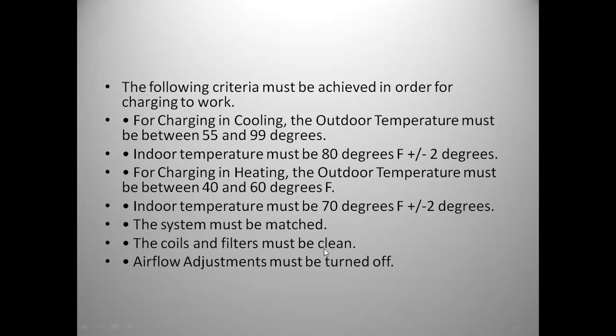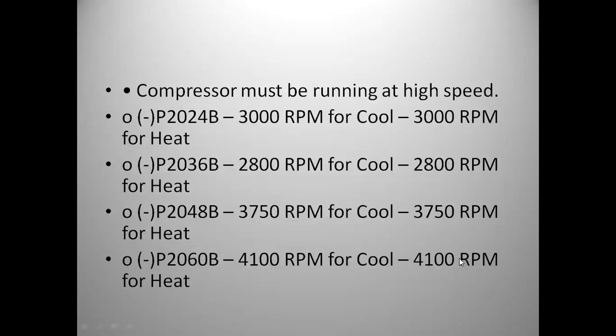The coils and filters must be clean. If they're not clean, it will skew your readings and affect your charge. And then all airflow adjustments must be turned off. And this is a big one. Ran into this the other day. Similar to a two-stage air conditioner or two-stage heat pump, these inverters must be running at the highest speed in order to check or adjust charge. If you're not running at the highest speed and it's not stabilized, by the time it does run at high speed and does stabilize, you may very well be way overcharged.